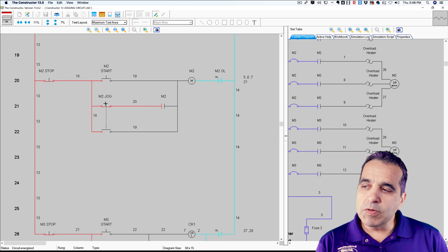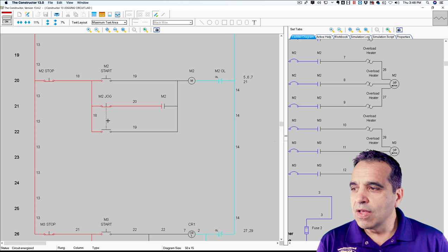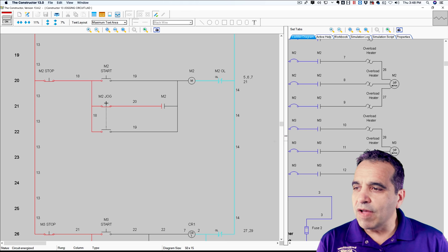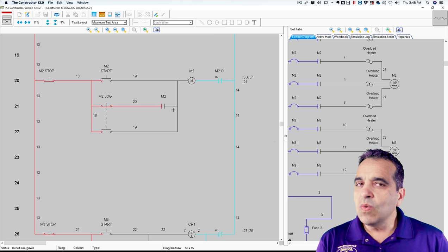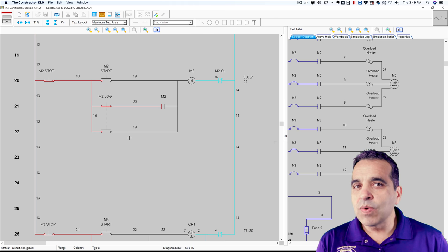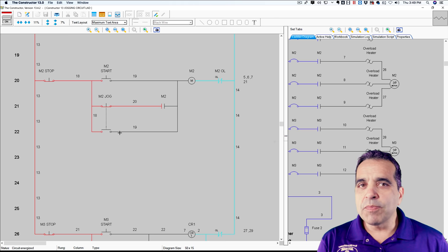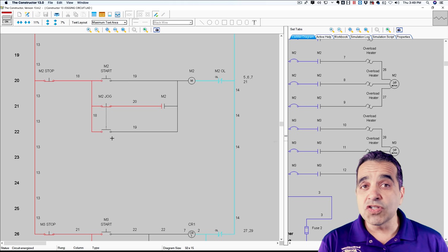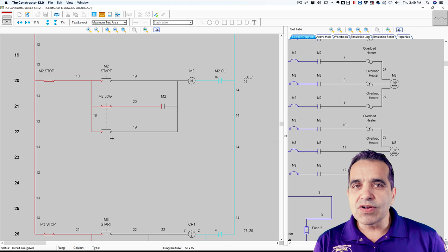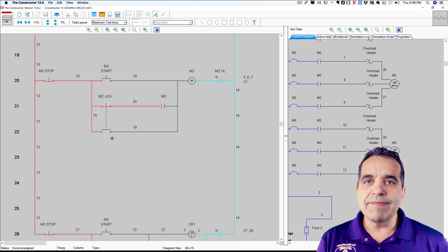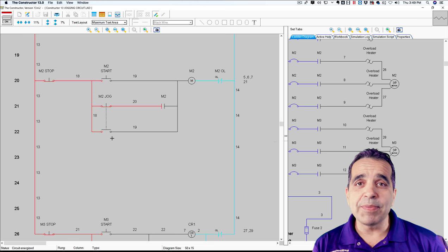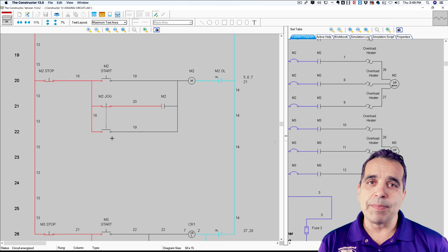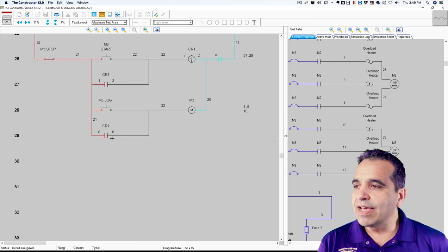All right. Sometimes people don't like this kind of a circuit, only because if your finger slips off this button relatively quickly, once in a while, the motor can stay running. And that would be a problem. If the spacing between these contacts isn't large enough, it might bridge that circuit. I've never really had it happen to me, but I know that it can happen. And then finally, a third form of this circuit, we're using an ice cube relay.